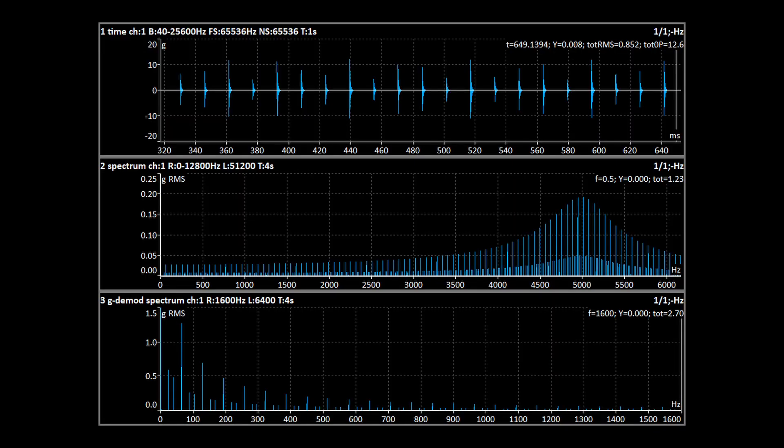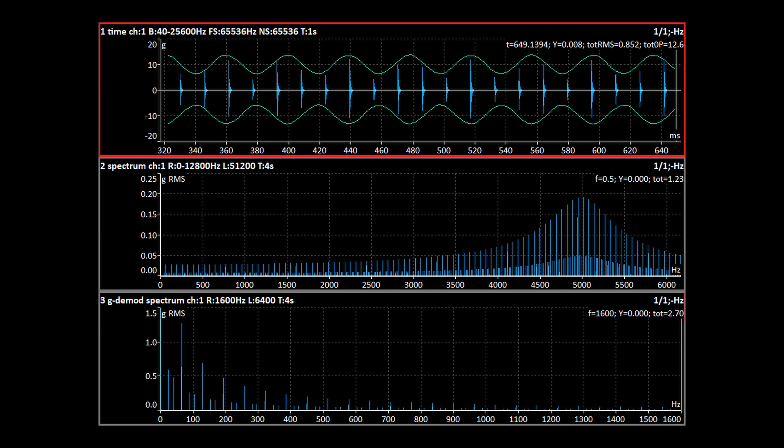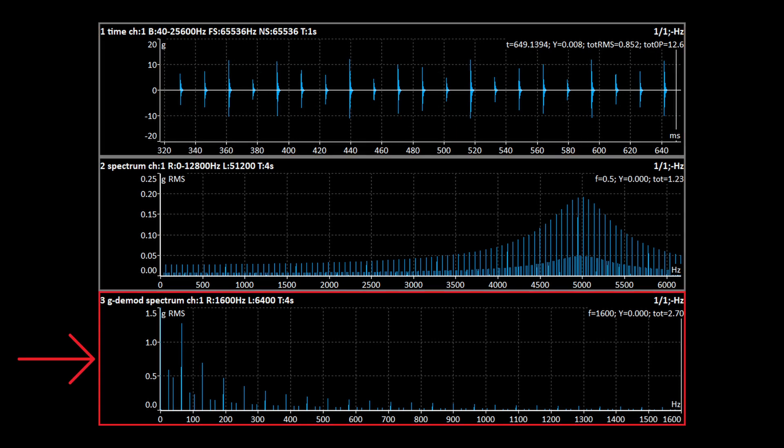Let's look at a measurement of a bearing with only one fault on the outer race. The time signal clearly shows the amplitude of the shocks is variable. It is modulated by the speed frequency of the rotating shaft. The demodulated spectrum shows the BPFO and its harmonics. Modulation is shown as sidebands near these frequencies.